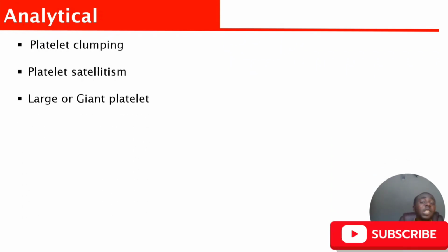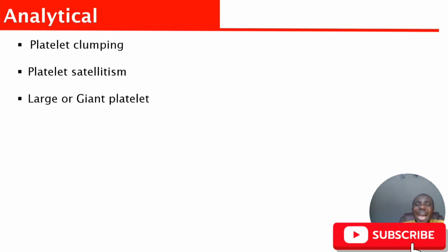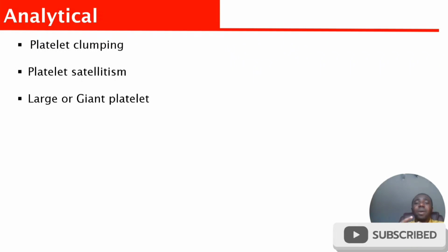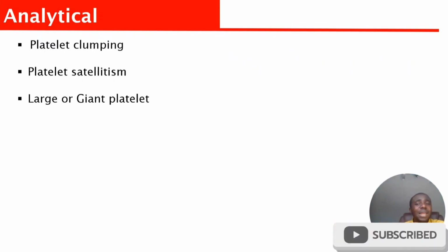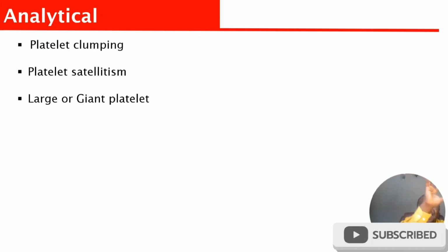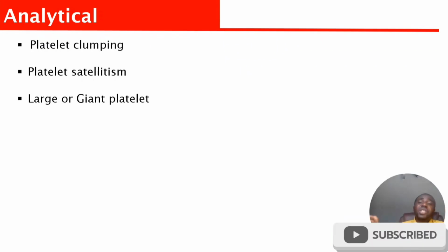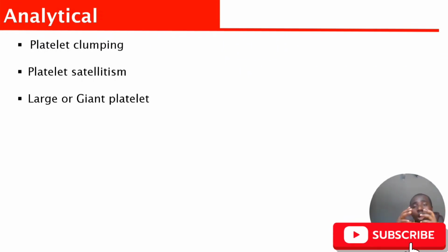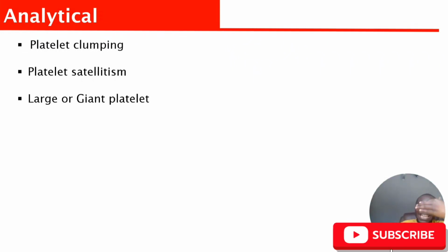Now, it could be due to large platelets or what we call giant platelets. Platelets have a normal size. If the size of the platelet becomes larger than required, the analyzer may not be able to count it as a platelet, because the analyzer is programmed to know the exact size of a platelet. Once the platelet is large, the analyzer may not count it because the size of that platelet has not been validated in that analyzer.